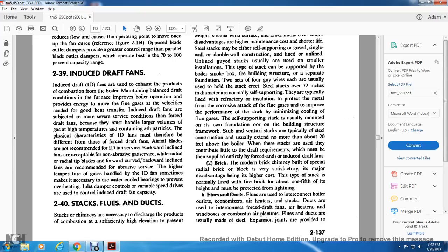239. Induced draft fans. Induced draft fans usually exhaust the products of combustion from the boiler, maintain balanced draft conditions in the furnace, improve boiler operation, and provide energy to move the flue gas at the velocity needed for good heat transfer. Induced draft fans are subjected to more severe service conditions than forced draft fans because they handle a large volume of gas at high temperature containing ash particles.